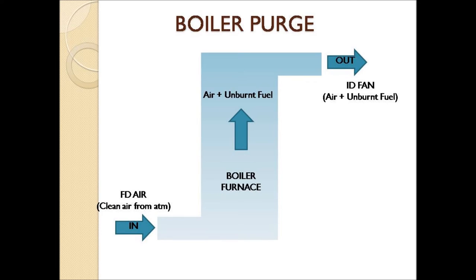The procedure of boiler purging is clearly shown in this picture. Clean air is provided by the forced draft fan, or secondary air fan, or FD air fan. This clean air is pumped into the boiler furnace. At the other end, the ID fan or induced draft fan creates a negative suction which pulls out this fresh air along with the unburned fuel and transports it to the stack or chimney. In this way, the unburned fuel is transported from the boiler furnace to the atmosphere.